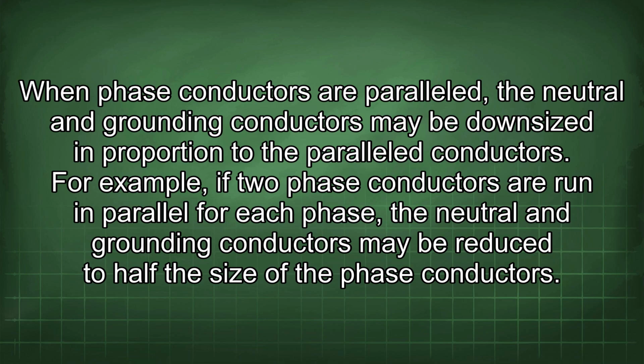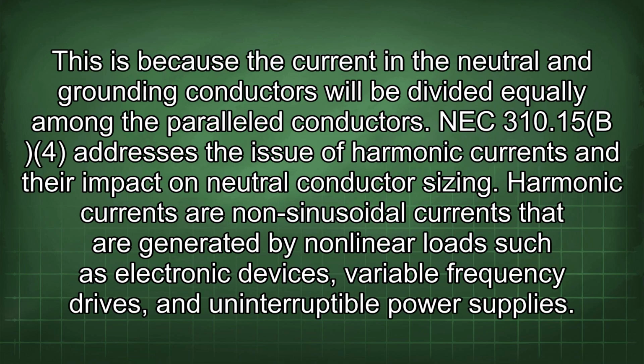For example, if two phase conductors are run in parallel for each phase, the neutral and grounding conductors may be reduced to half the size of the phase conductors. This is because the current in the neutral and grounding conductors will be divided equally among the paralleled conductors.